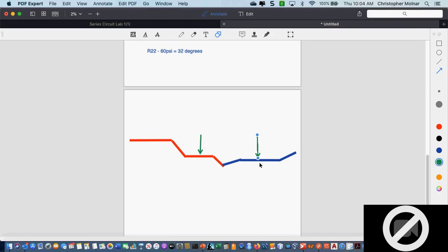Since the cycle never ends, can refrigerant ever be used up? No. Does refrigerant ever get destroyed under normal operation? No. If somebody goes out to a house and says 'you've used up your refrigerant, we have to put Freon into your system,' the only time refrigerant comes out of a system is if there's a leak — that technician is lying.